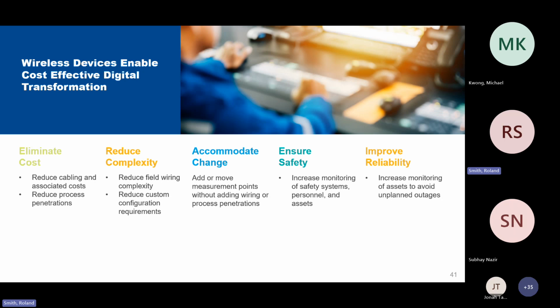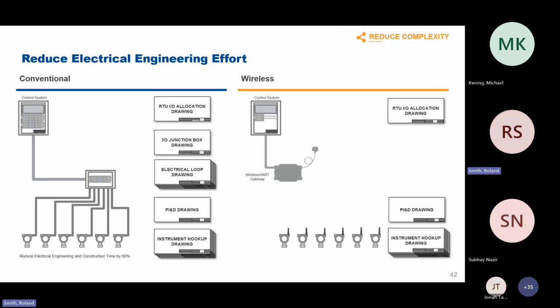A lot of our customers are running out of I/O, so analog inputs on older control systems are at a premium. When they add wireless devices, you simply get away from a lot of the conventional, traditional engineering and drawings that come with those type of projects. Really on the wireless side, you do the hookup drawings, its connection to the process, and that's it. There's no wiring diagrams, analog inputs, or anything associated with those type of devices coming back to the gateway and ultimately to the control system.